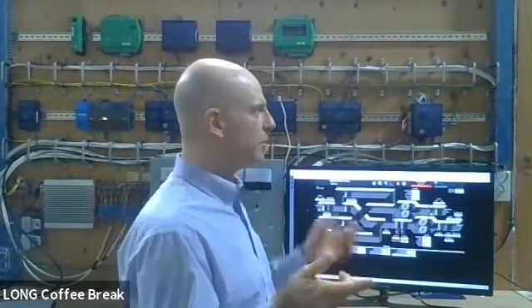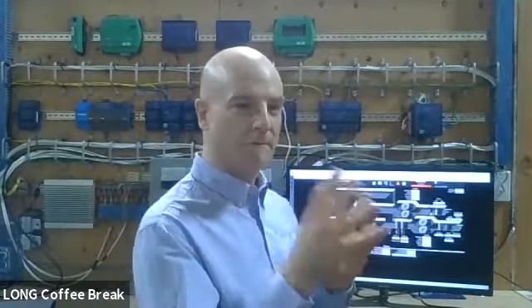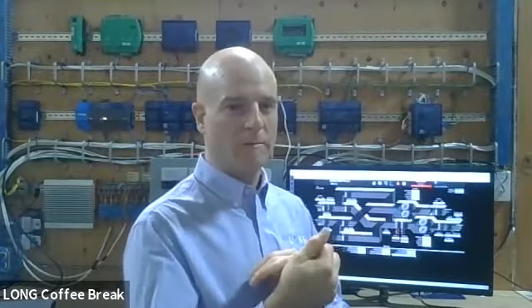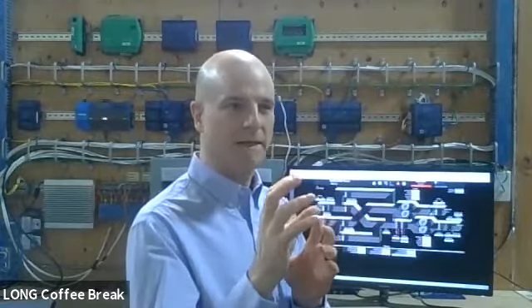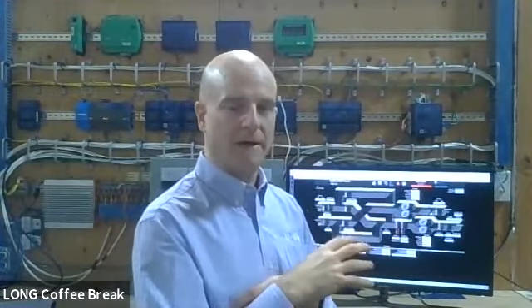But so we'll test every what we call a typical program or a template program. So if we have 12 air handlers that are all the same, we only do one test. We test the one template program for that air handler. We test the VAVs program. We test the exhaust fans, the fan coil units, the heating water hydronic system, the cooling water hydronic system. Every main component that has a program, we're running through the sequence of operation right here on this bench.